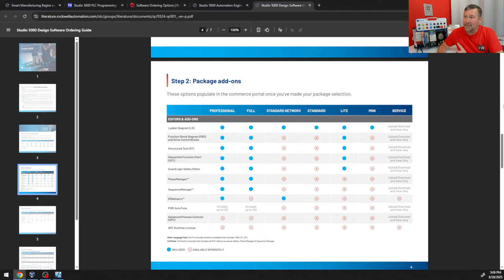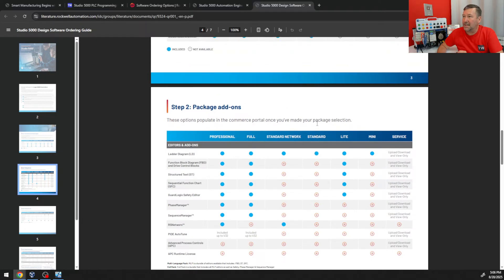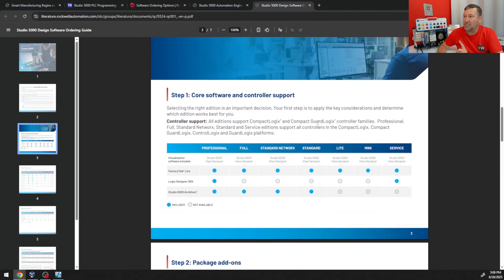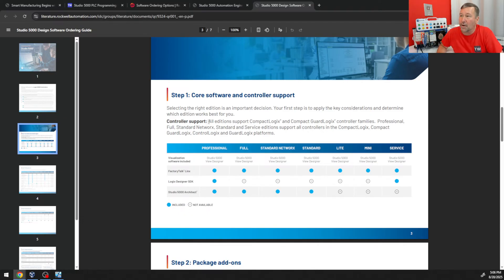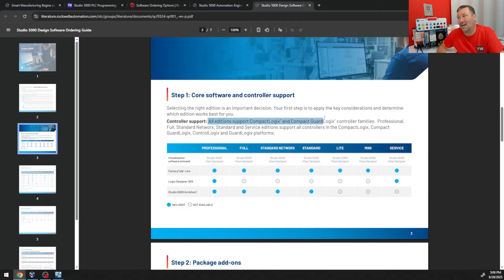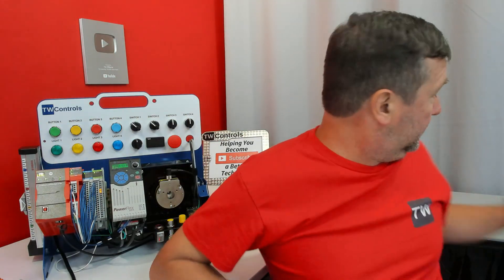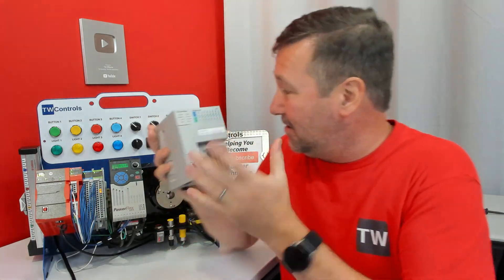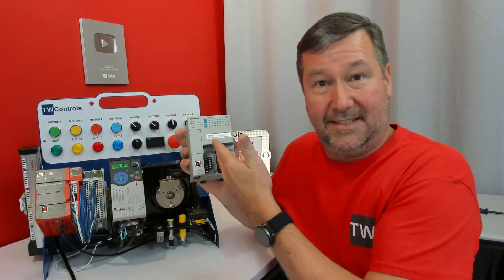Now let's talk about one other thing — because I blow up over it every time — there is one little hitch we need to look at on page three: controller support. All editions support the CompactLogix and CompactGuardLogix family of controllers. So any of these we can use with the CompactLogix or the CompactGuardLogix PLC — they work fine.